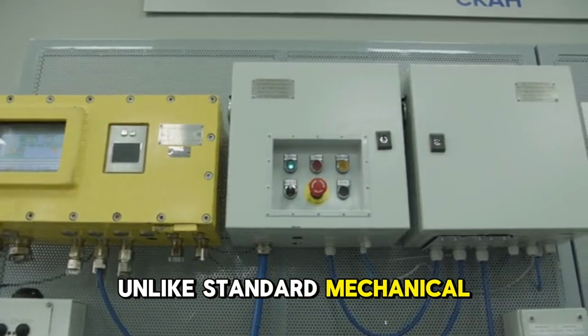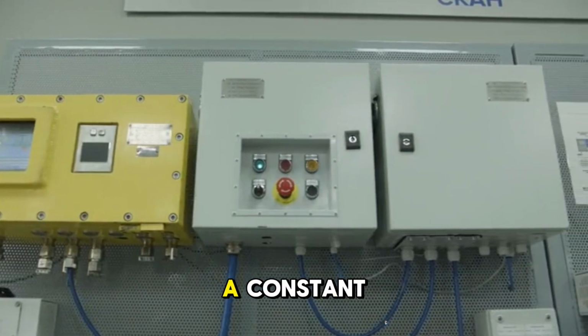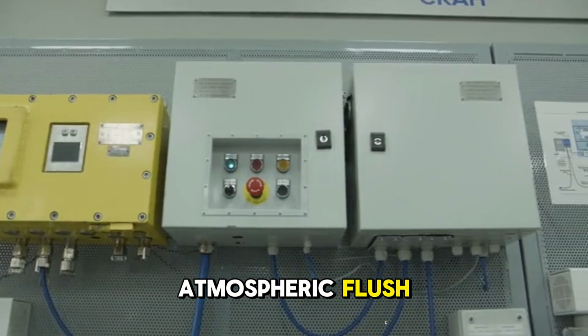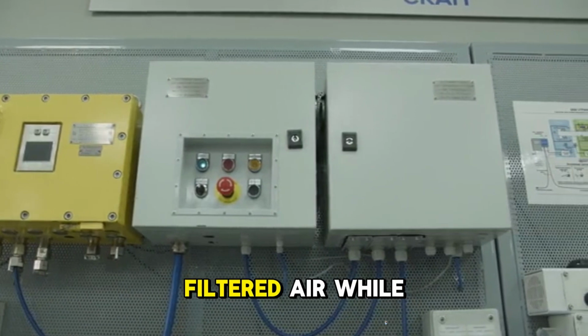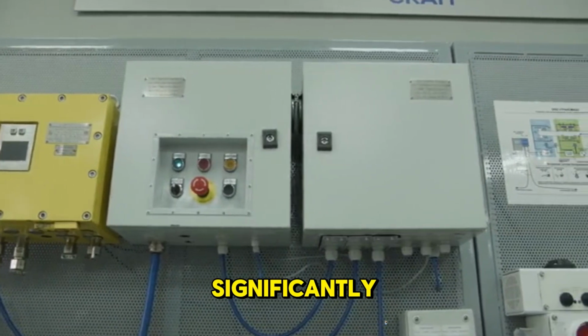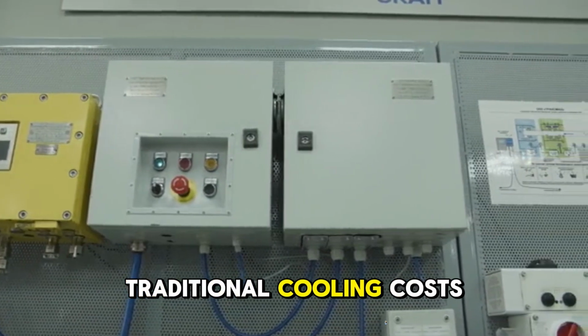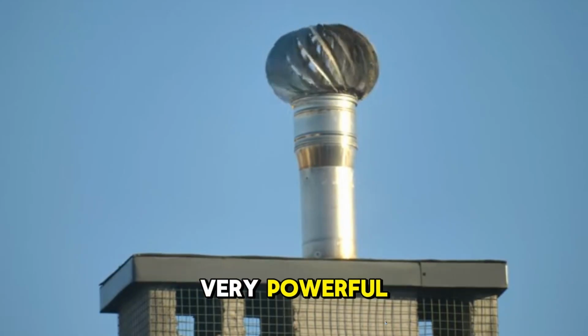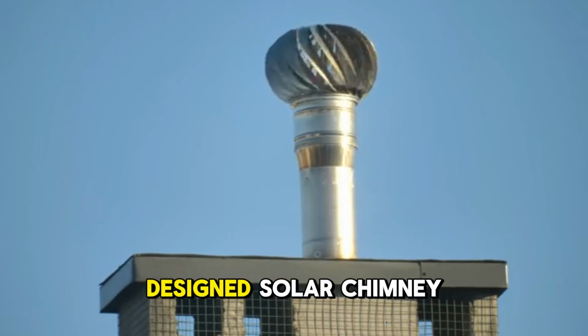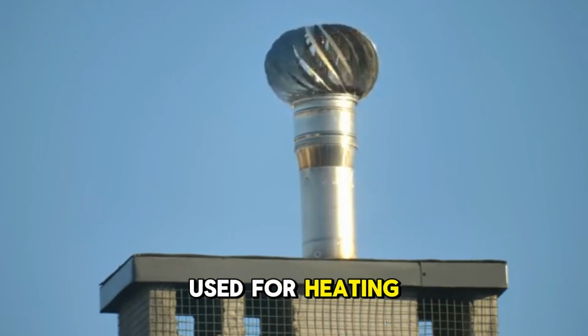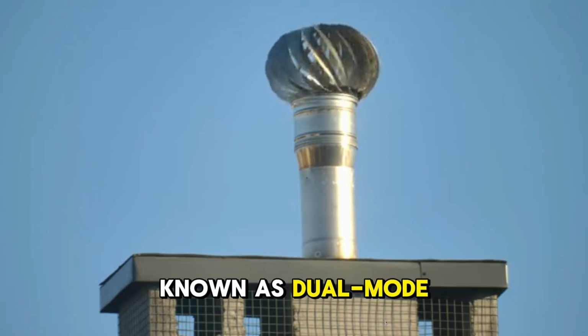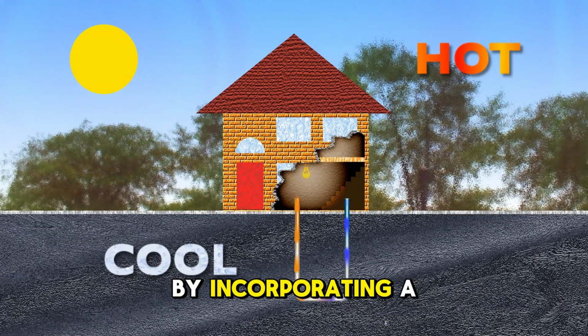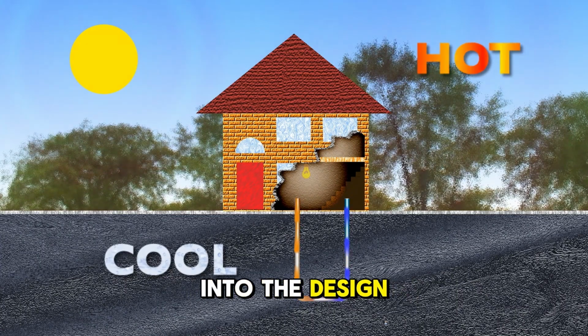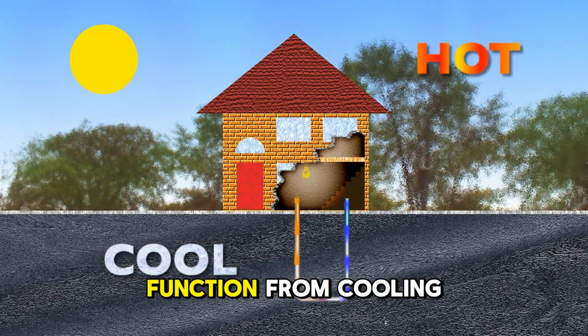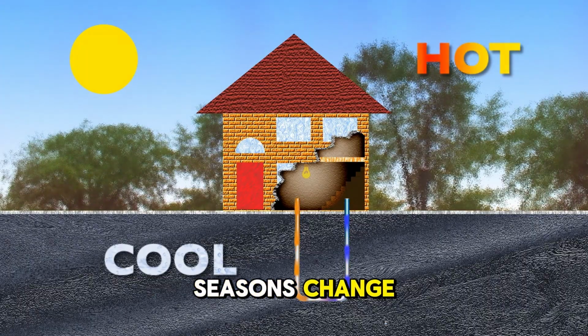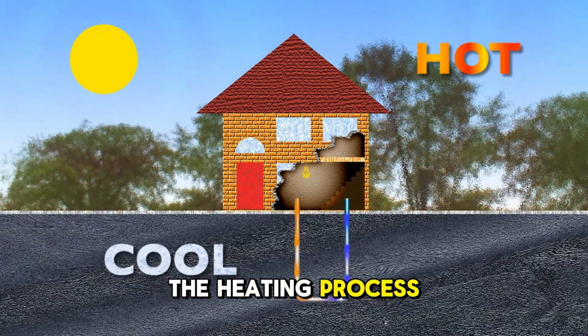Unlike standard mechanical systems, this setup provides a constant atmospheric flush, delivering 100% fresh filtered air, while significantly reducing or eliminating traditional cooling costs. The interesting and very powerful part of this is that a properly designed solar chimney can be used for heating in the winter through what is known as dual-mode engineering. By incorporating a bypass damper into the design, you can switch the system's function from cooling to heating as the seasons change. Here is how the heating process works.